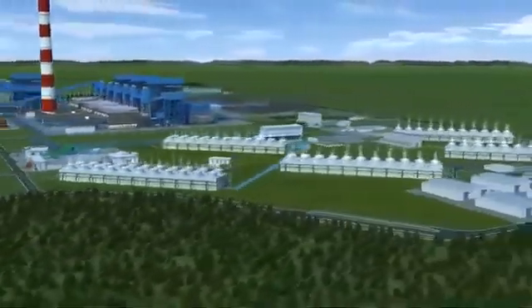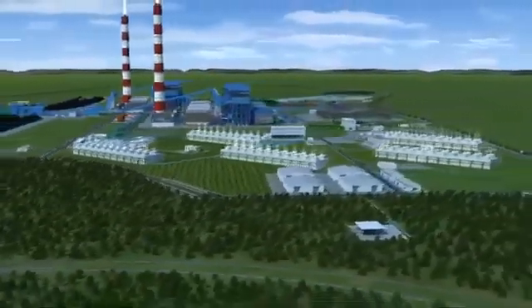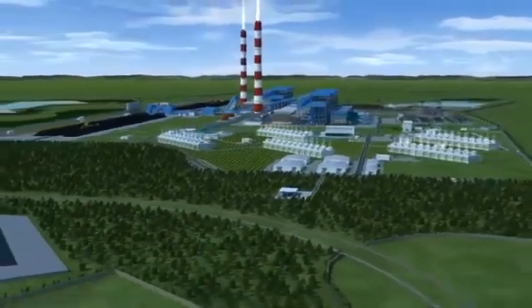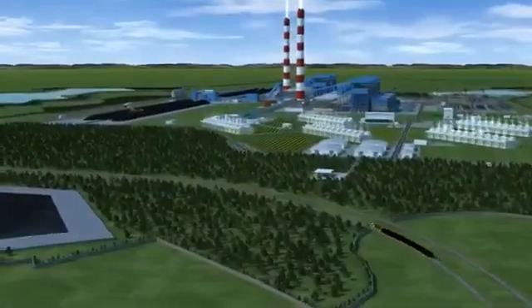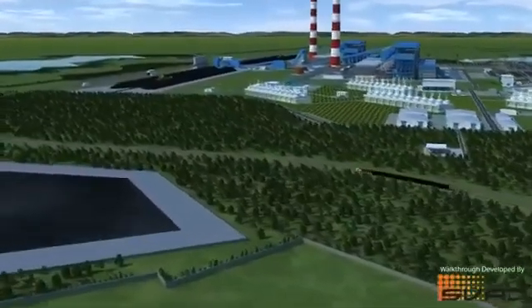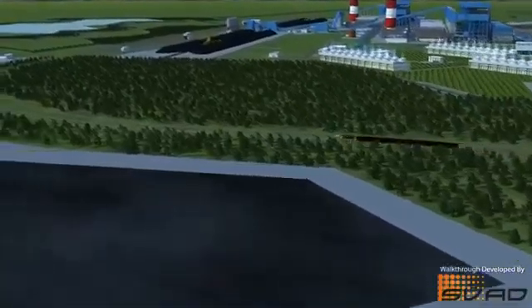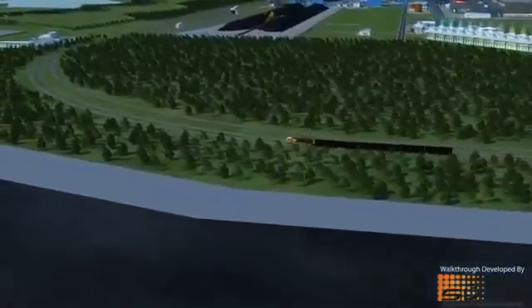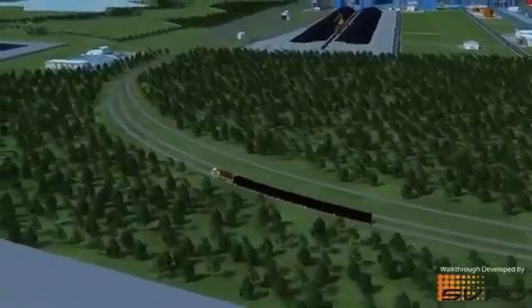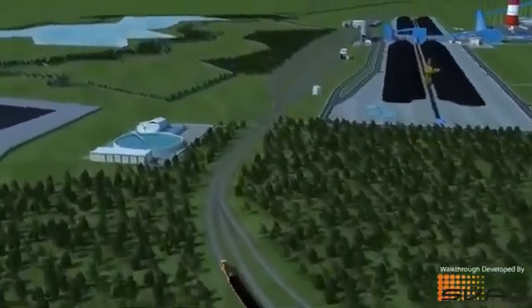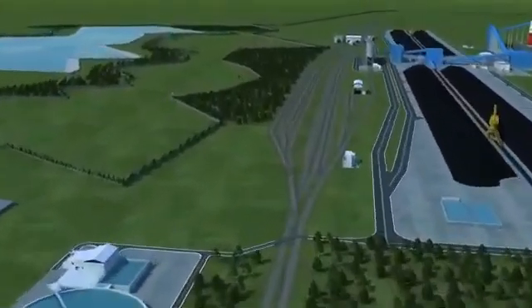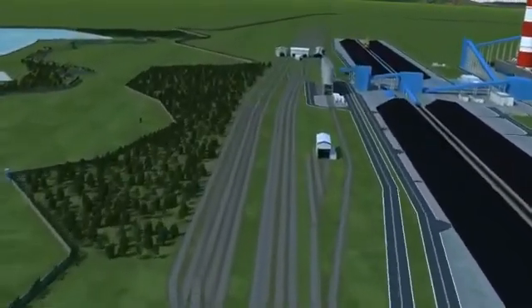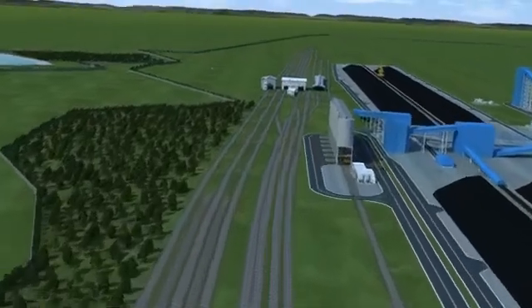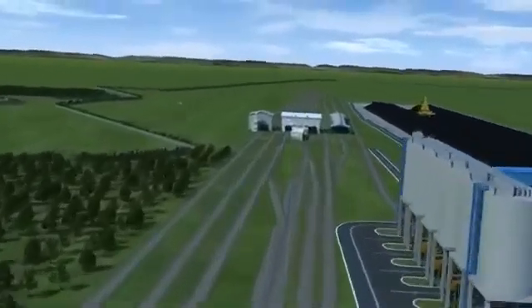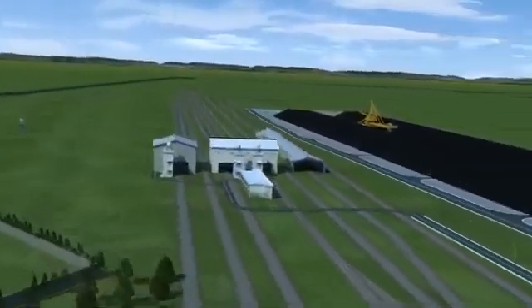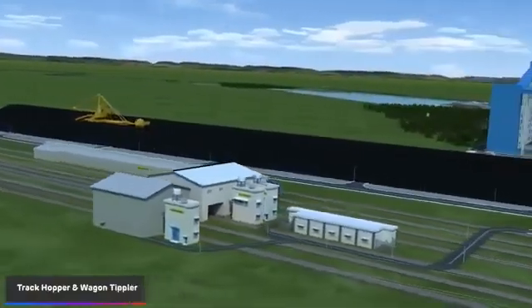At a full load of 3,300 megawatts, Tiroda Power Plant will consume about 48,000 metric tons of coal per day. On an annual basis, about 15 million metric tons of coal will be needed for Tiroda Power Plant. Coal for the plant is received through a rail connectivity, taking off from Kachargadh railway station at about 3 kilometers from the location of track hopper wagon tipplers located at south of plant. The entire civil works has been done by Messrs. Gammon India Limited.